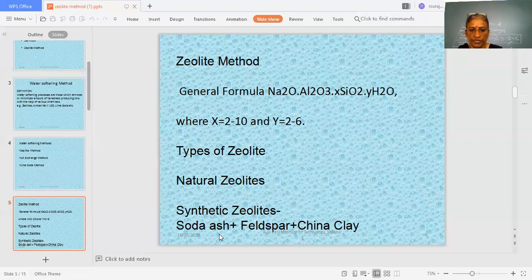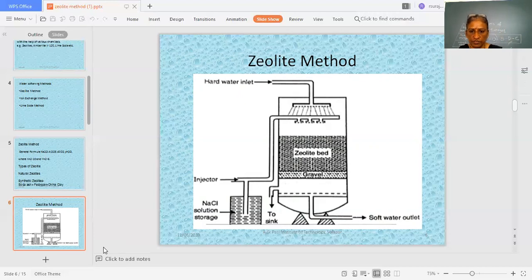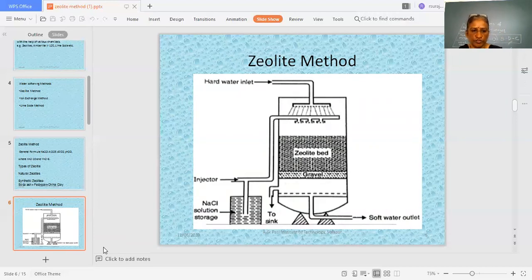Synthetic zeolites have many pores and have capacity to exchange ions. The principle behind the zeolite method is that water is percolated through a zeolite bed at a specified rate. Whatever hardness-causing ions are present — calcium and magnesium ions — those are exchanged and replaced by sodium ions. They are trapped in the pores of the zeolite and the water gets softened.